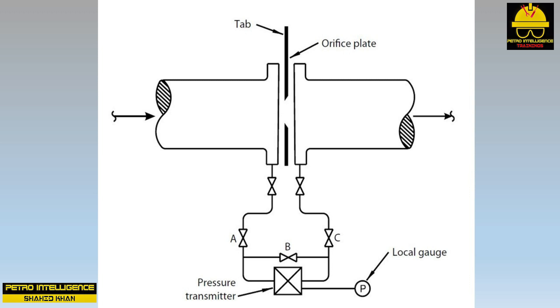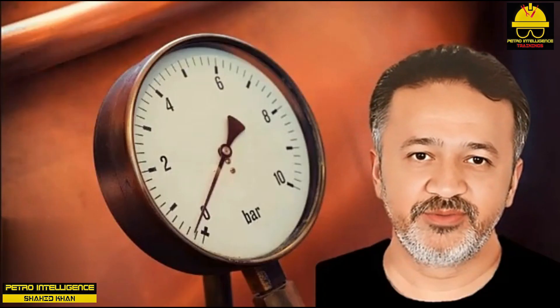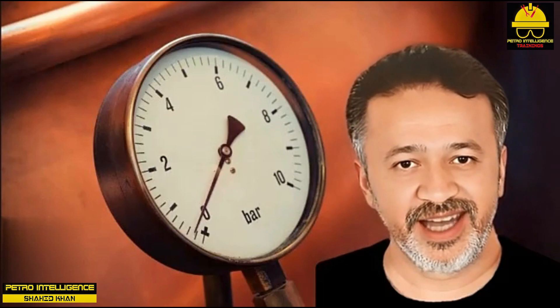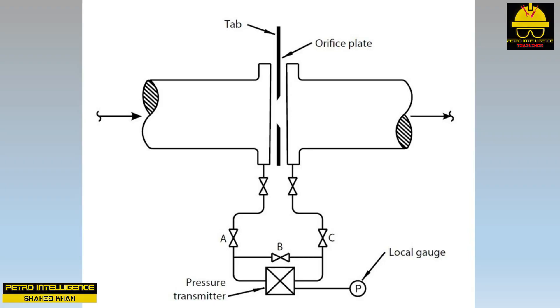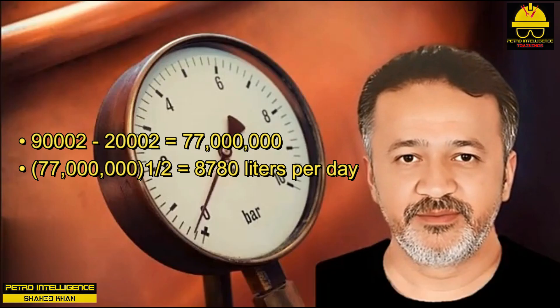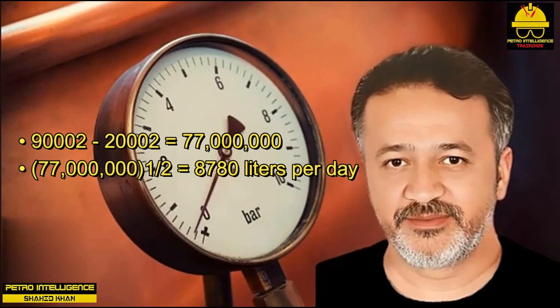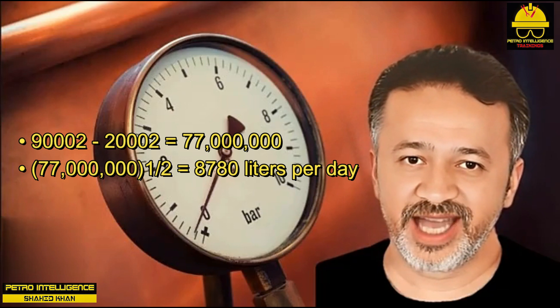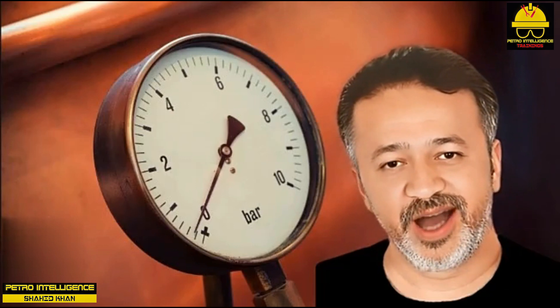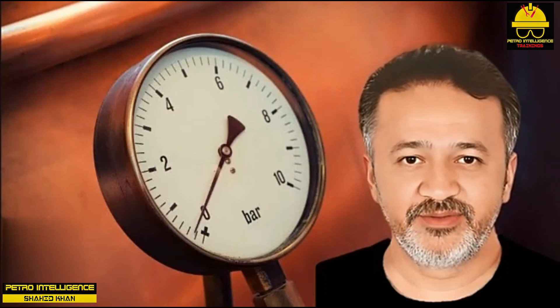Open valve B and close valves A and C, then wait until the flow meter indication stops changing — it should go back to zero if the lines are refilled. Zeroing the flow meter: the indicated flow of acetic acid is 9,000 liters per day. The technician checks the meter by opening valve B with A and C closed — it should read zero but reads 2,000 liters per day. The full range is 10,000 liters per day. The real flow is not 7,000 liters because flow varies with the square root of orifice plate pressure drop. The correct calculation is: √(9,000² − 2,000²) = √77,000,000 = 8,780 liters per day.